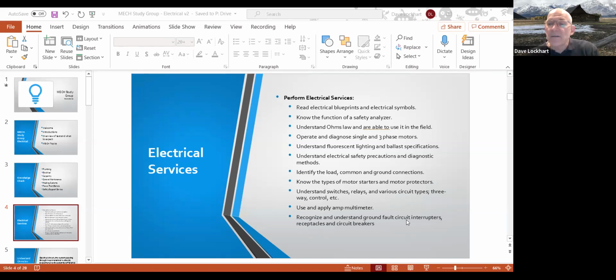Circuit breakers, I mentioned, you got lots of different types of circuit breakers. I don't know whether they cover simple installed, racked-in type of breakers, removable breakers, and their different settings and trip functions. We kind of covered that. We did cover identifying load, common, and ground connections, electrical safety precautions, again, lockout, tagout, testing, making sure systems are de-energized before you do anything, diagnostic methods of testing electrical circuits, making sure things are safe, turned off, amperage readings. I think we covered all of these other items here.